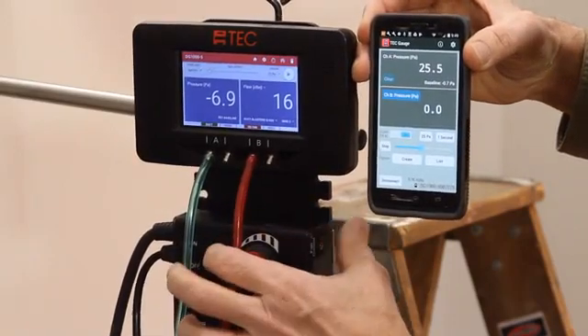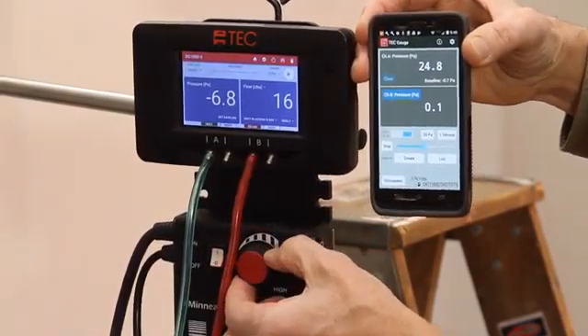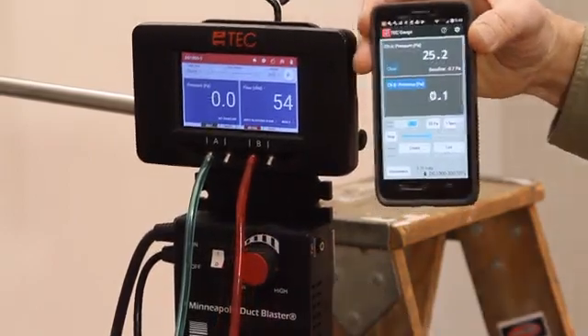Gradually increase the fan speed until the pressure shown on channel A is zero pascals. Record the CFM flow from channel B.